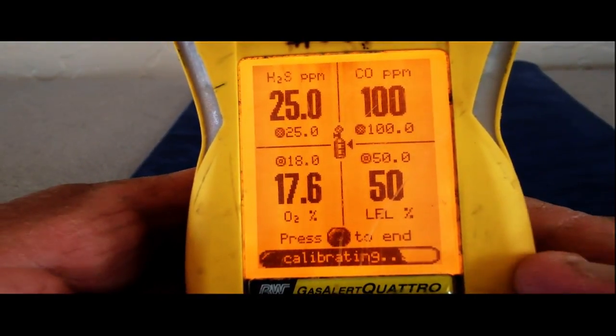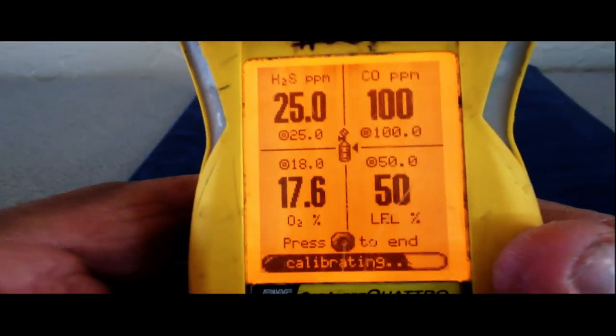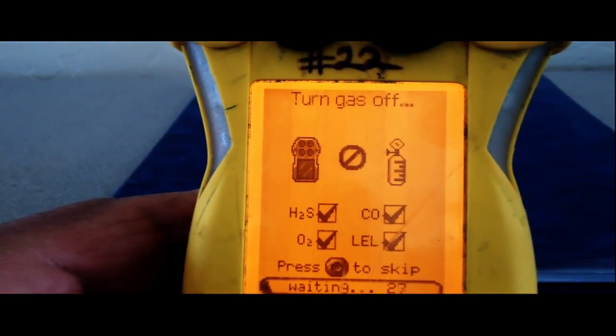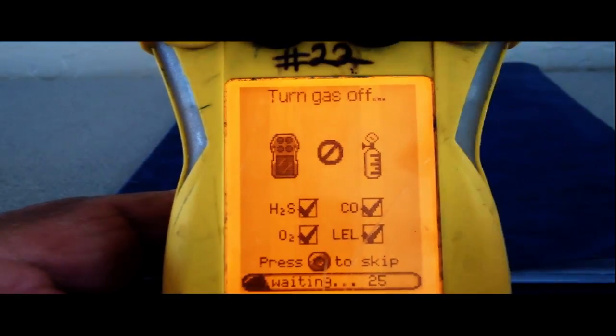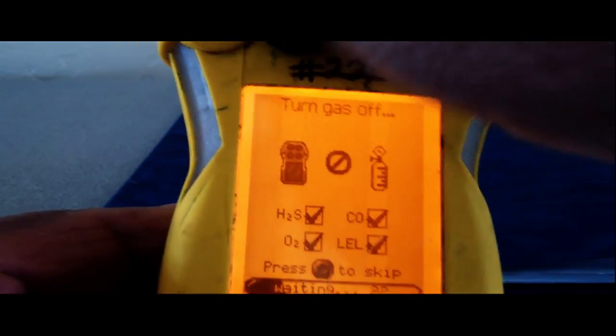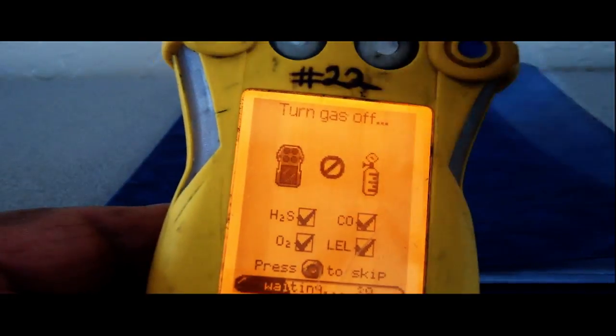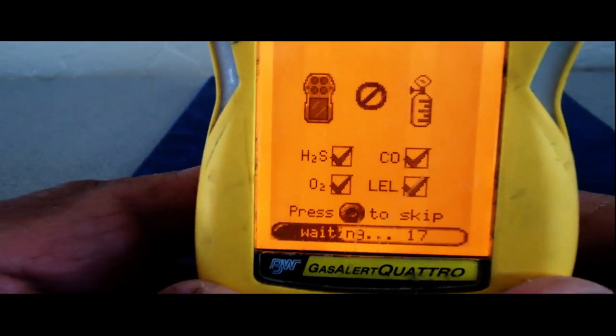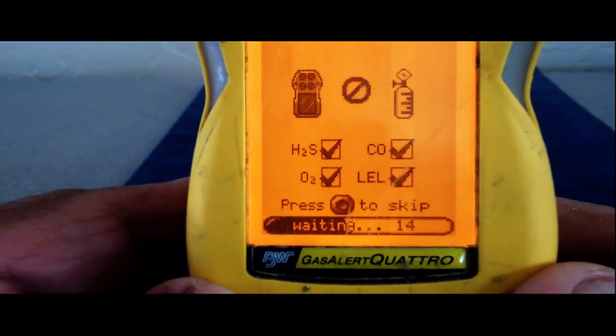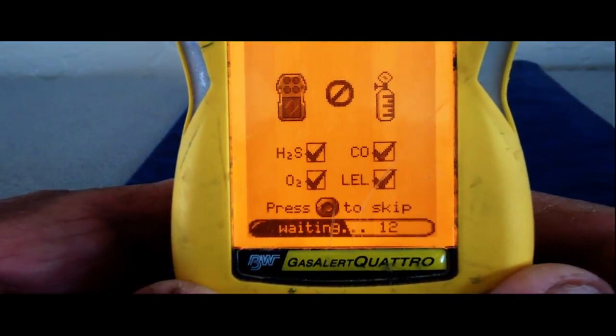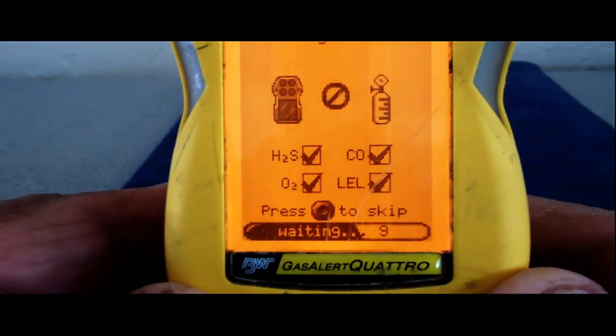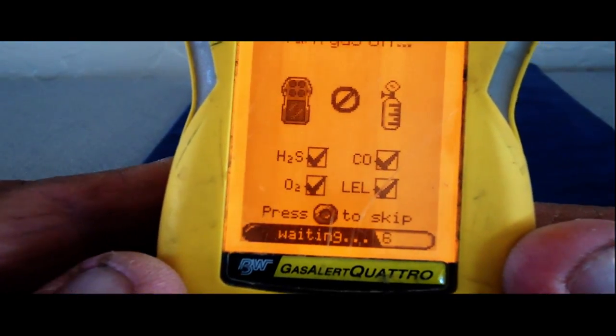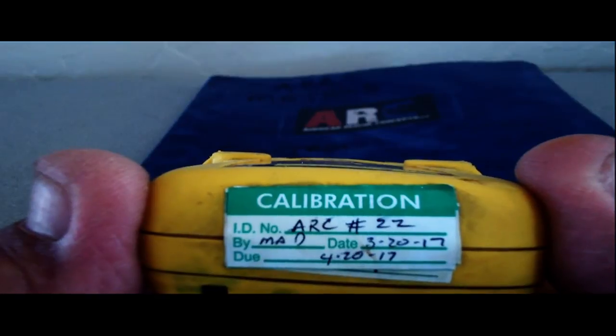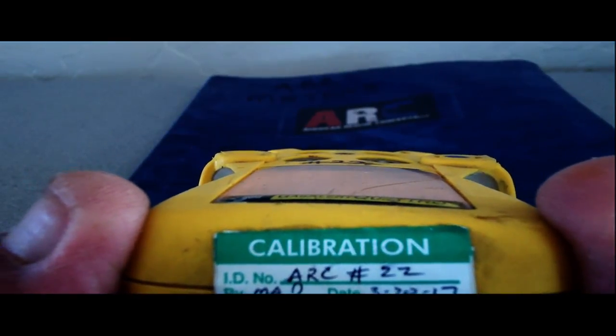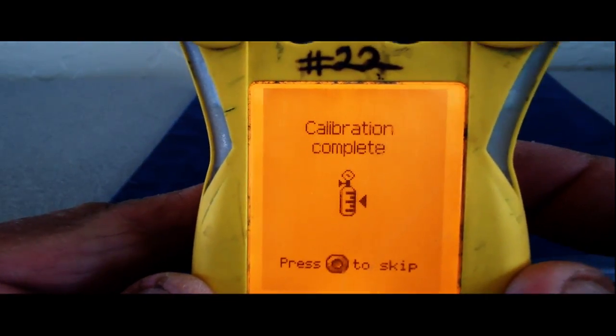So we're getting close. Remember, once we get there, we're going to turn that gas off like it says. That gas is quite expensive, so turn it off first. Remove your calibration cap, and it's going to continue going through its calibration phase. Once we calibrate these units, we put a calibration label on it to indicate when the next calibration is required. Bam, calibration complete.